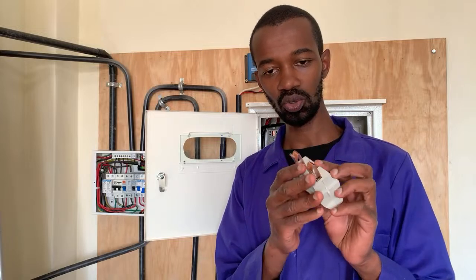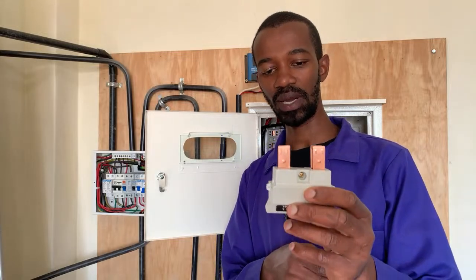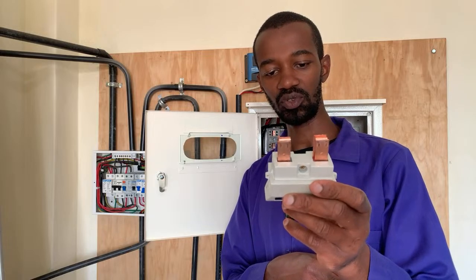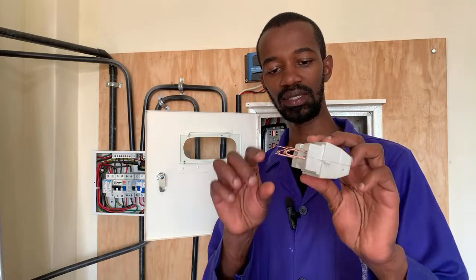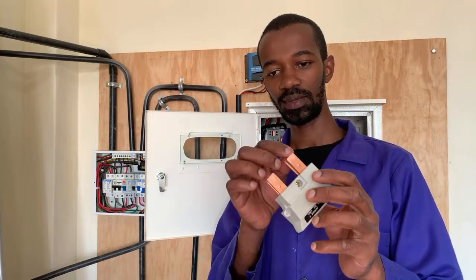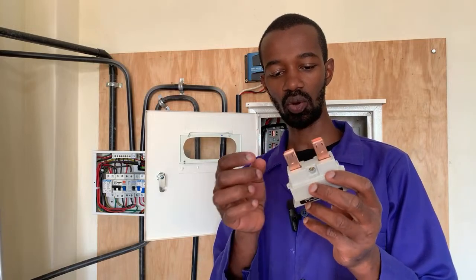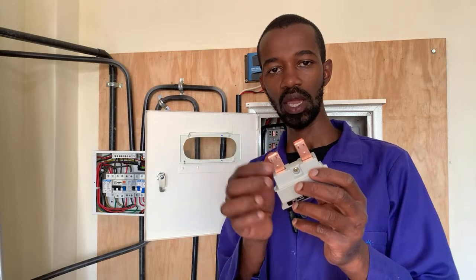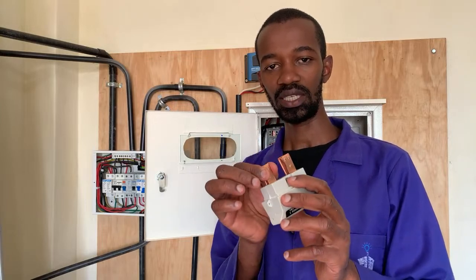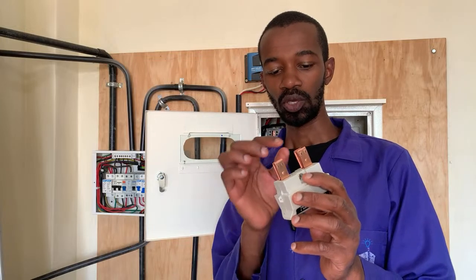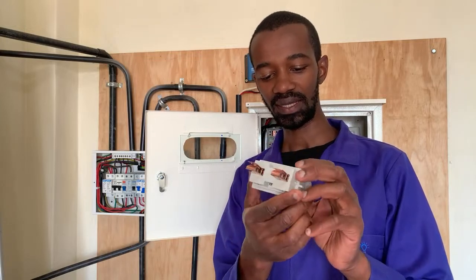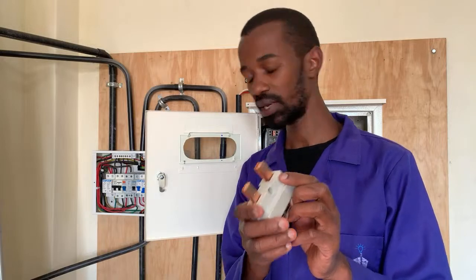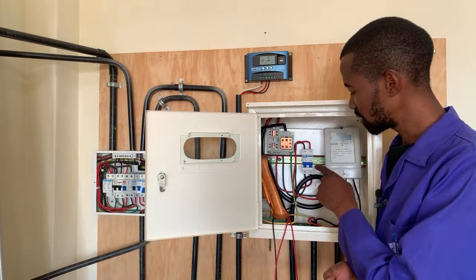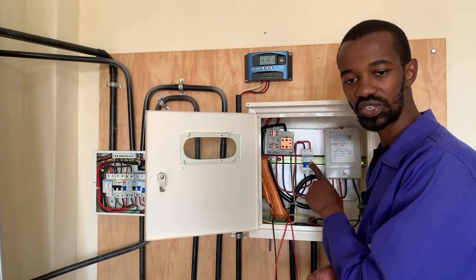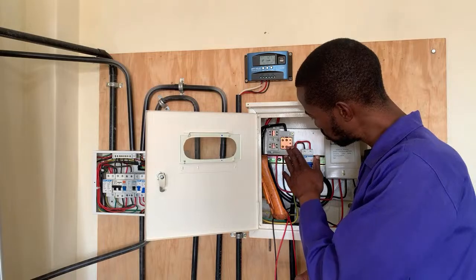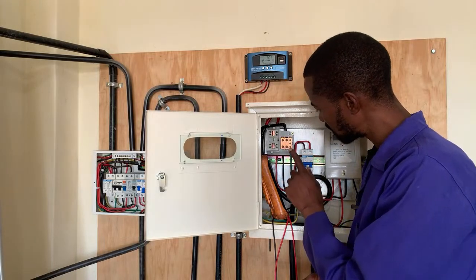If everything looks good, like with this cutout fuse carrier, these copper plates are looking good, meaning there is no issue of arcing or burning that normally happens when there are electrical issues at the cutout level. Once you detect things are okay here, the meter is not powered, the main switch has not tripped, and everything looks okay, then it means there is a problem.